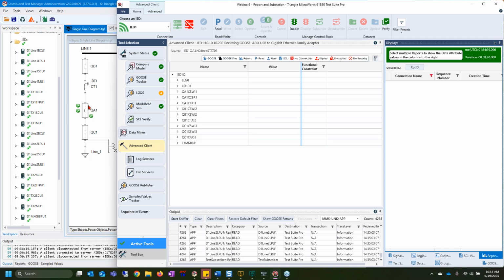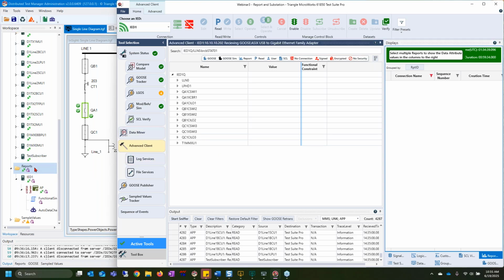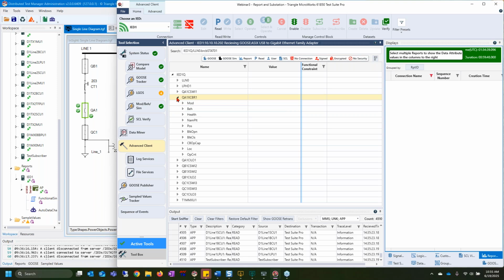So let's go ahead and start seeing what this would look like from the client side of the tool. To do that, I'm going to go over to the advanced client, and I'll be looking inside of IED1 here. And so you have your logical device, all of your logical nodes. Then we can do something like go into the XCBR. The BR in XCBR stands for breaker. So if we go in there, we can see all the data objects associated with the XCBR, including things like blocking, open and close, and position.